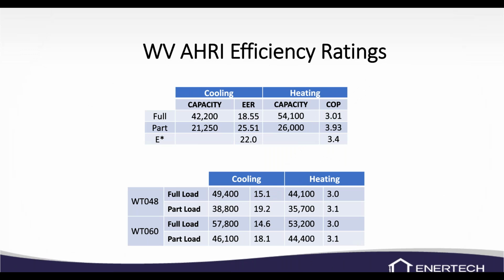Here are some capacities. If you look on the top chart, these are the 060 ratings. And then you can see, compared to our standard 2-stage water-to-water unit capacities, the EERs and COPs of the unit. So definitely more efficient. Capacity is pretty much the same as the WT060, so capacities aren't really a real factor there.